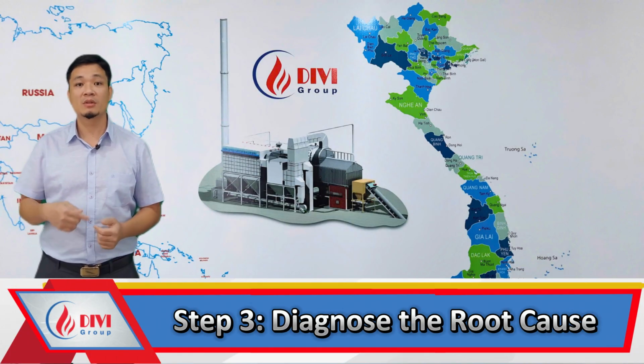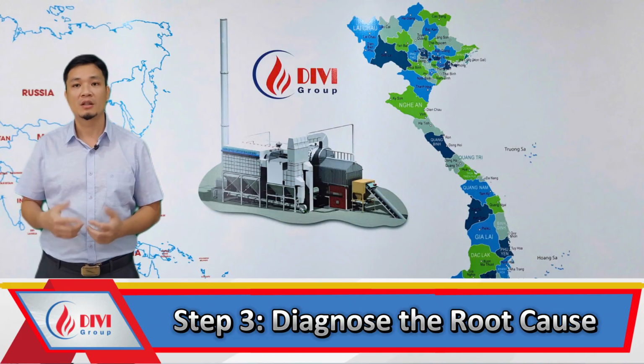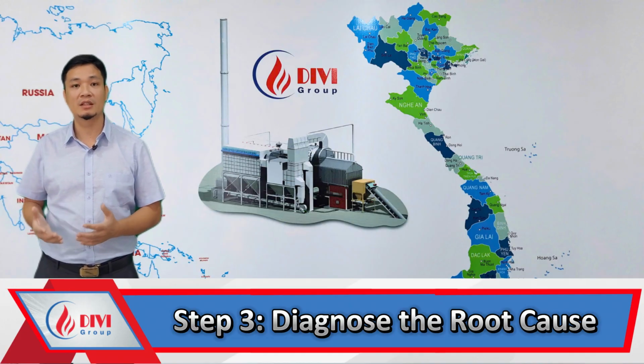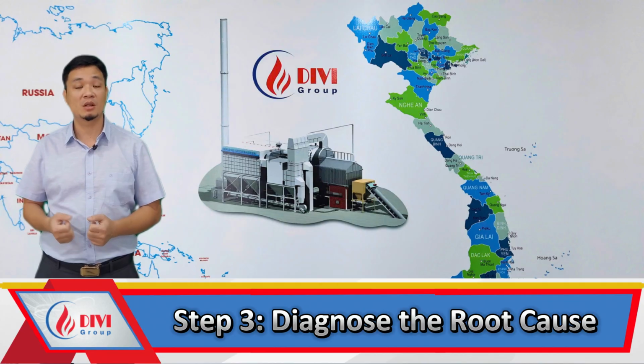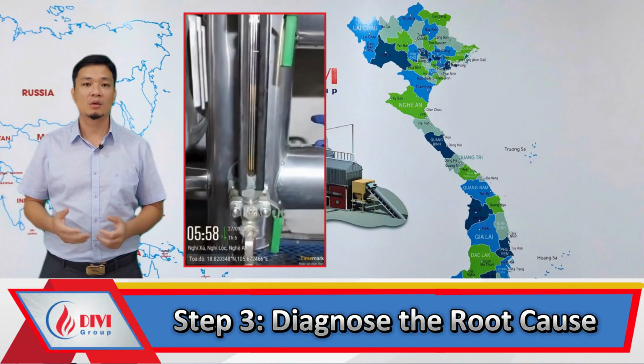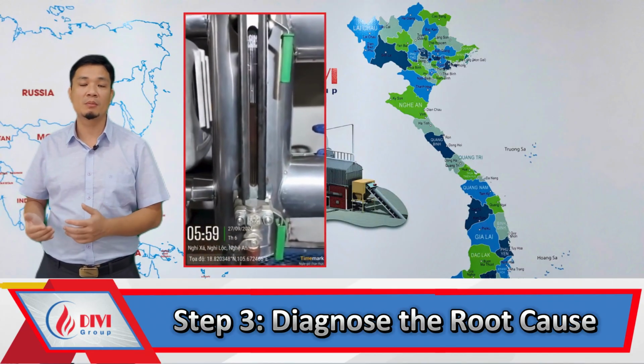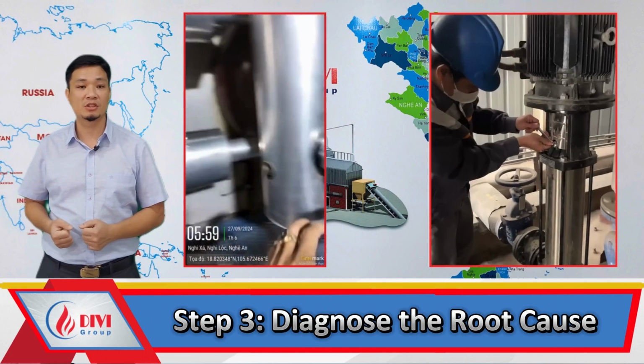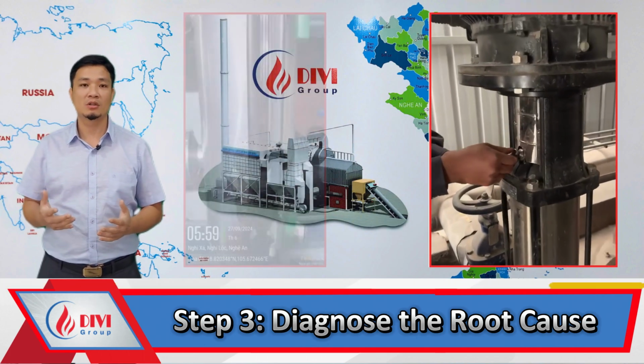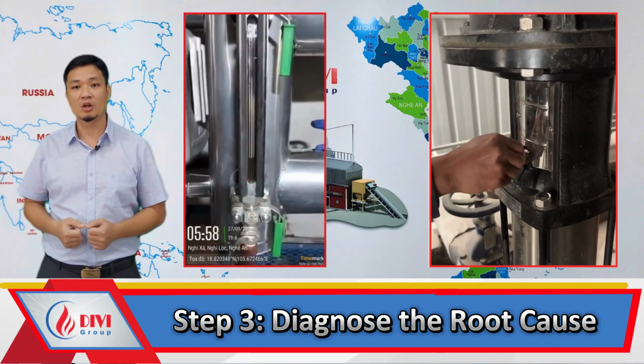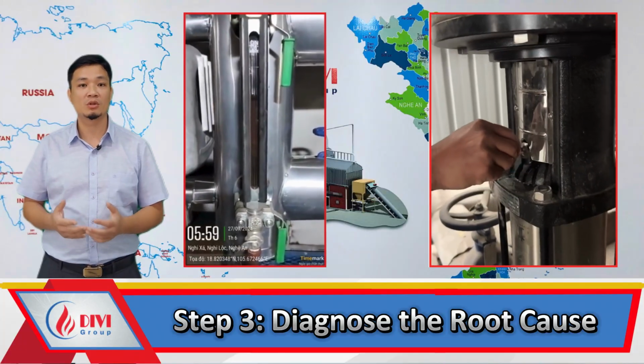Check the water level in the sight glass and look for any anomalies in the water level sensors. Inspect whether the feed water pump is operational or burned out. Open the air vent valve on the pump and thoroughly inspect the piping system to identify the root cause of water loss, such as clogged lines, leaks, or faulty valves.